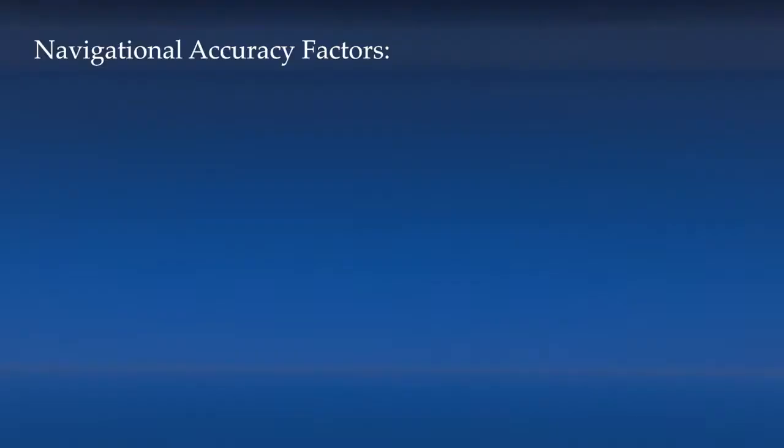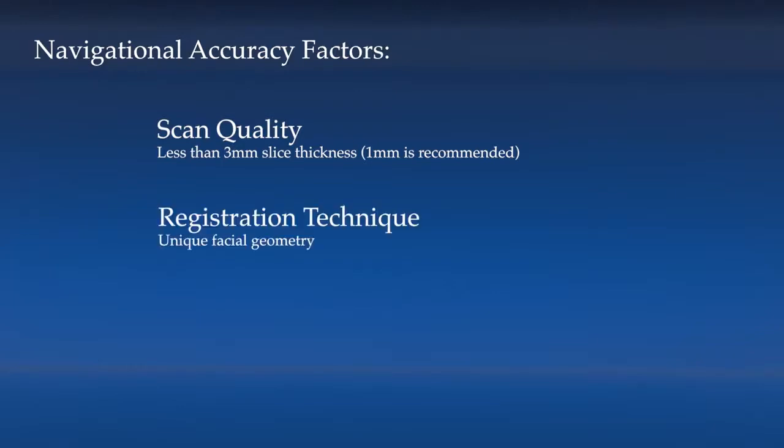There are three primary factors affecting navigational accuracy that are important to remember when using any neuronavigation technology. The first is scan quality. A low-resolution scan makes it very difficult for the computer to match points on the scan to the patient anatomy. Second is registration technique.